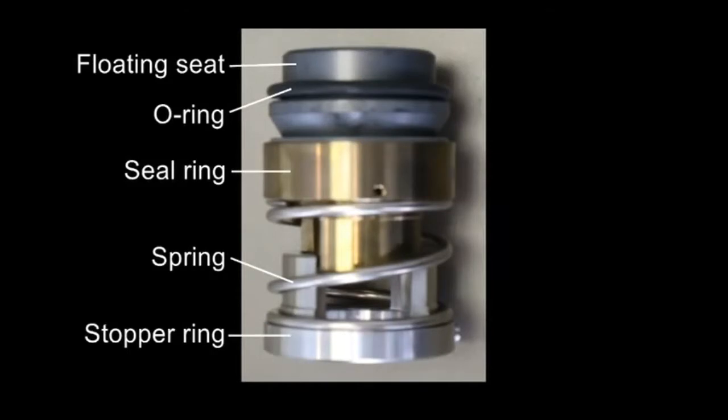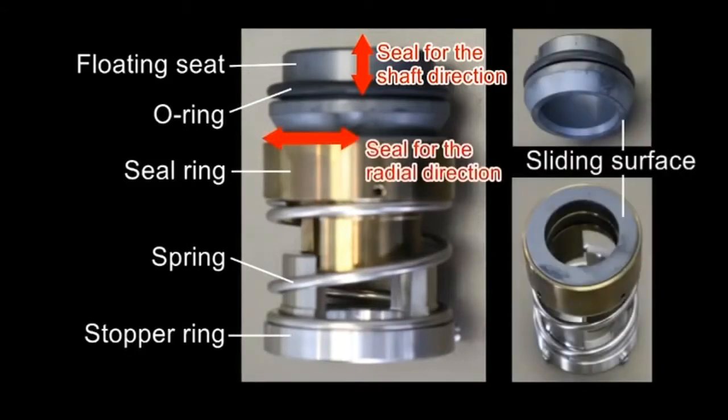The mechanical seal keeps air tightness by a combination of sealing in the shaft direction by the shaft fixed O-ring and sealing in the radial direction by the sliding of the seal ring and floating seat.